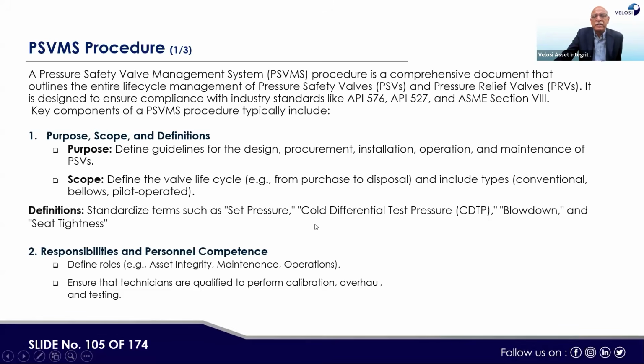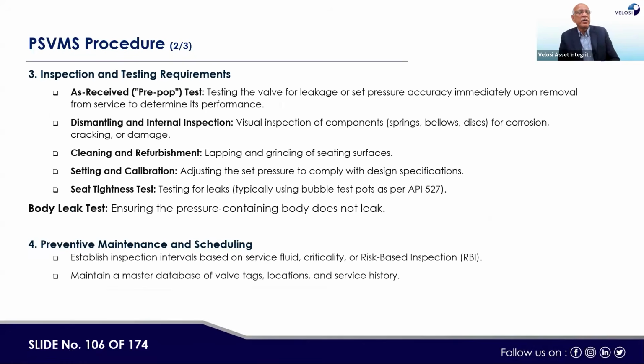Definition: standardization of terms such as set pressure, cold differential test pressure, blow down, and seat tightness. Responsibilities and personnel competencies are also covered under this document. Define roles, for example, asset integrity, maintenance, and operations, and ensure that technicians are qualified to perform calibration, overhaul, and testing. Then inspection and testing requirements: as received, pre-pop test, dismantling and internal inspection, cleaning and refurbishment requirements, setting and calibration requirements, seat tightness test requirements, body leak test requirements. So all these inspection and testing requirements are specified in this particular document.